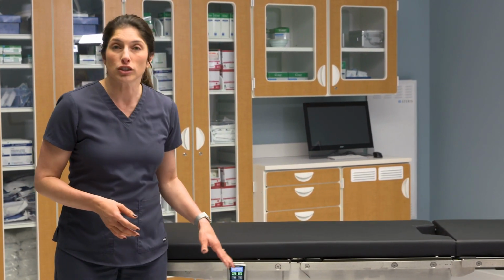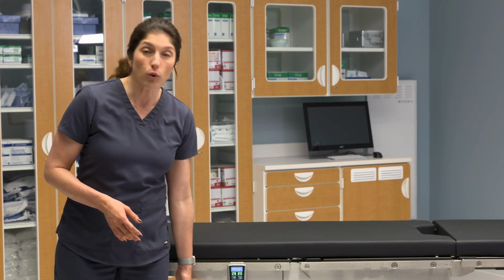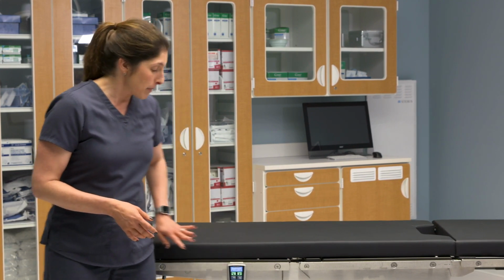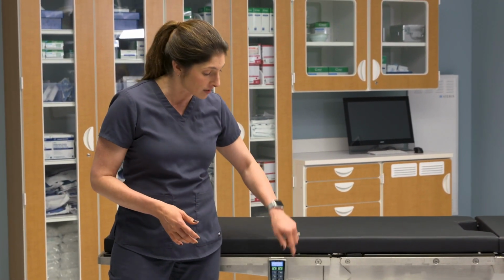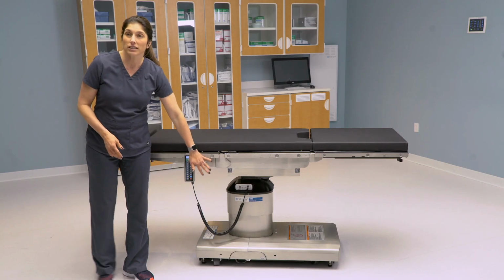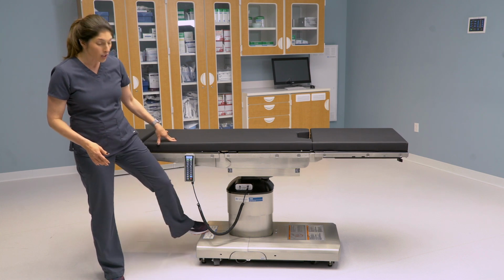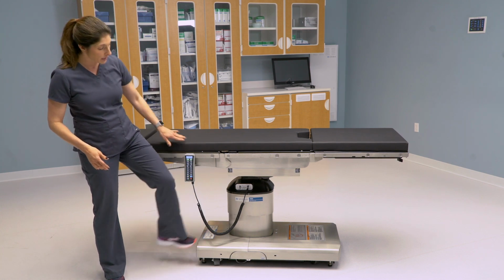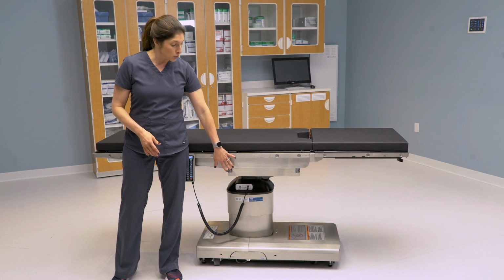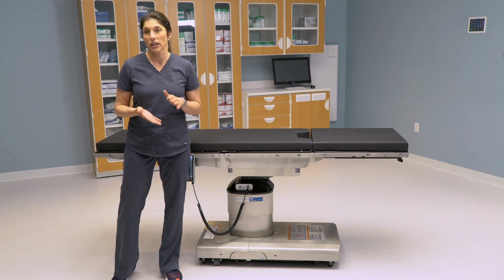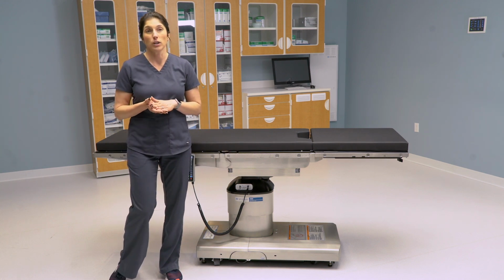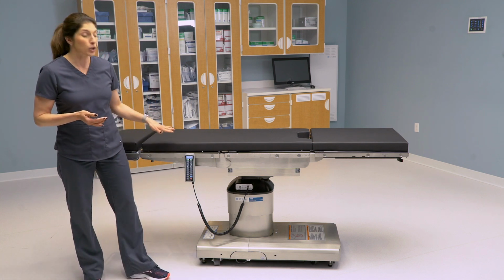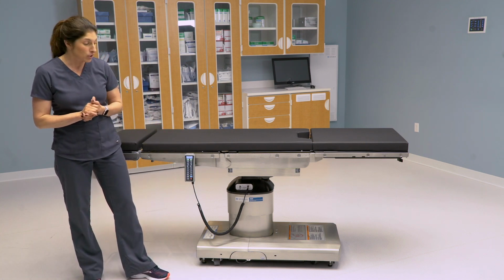It can be quite problematic on the 4085, so I want to encourage you and anesthesia to put that SCD either on the floor in front of the base, hang it on the side rail, or find an alternative location for it, because when it gets placed on this base, patient's draped, nobody can tell where that is, and it gets pushed up against this column and the shroud, and when the table is raised and lowered, it can crack that shroud and cost you money to replace. So I would encourage you not to place your SCD on the base.